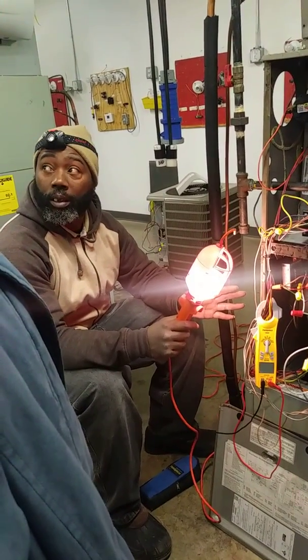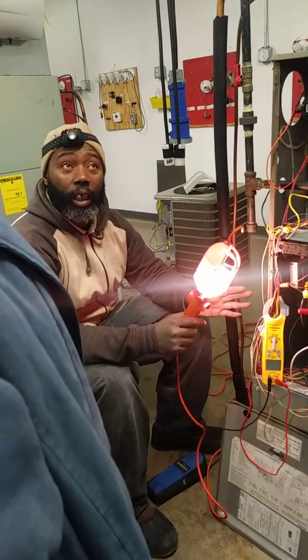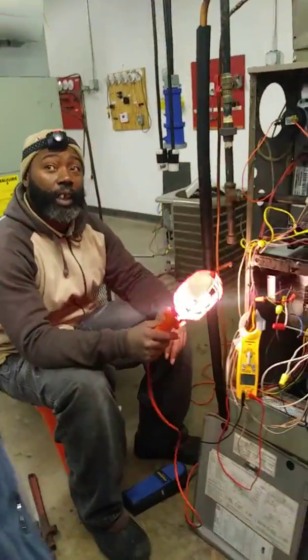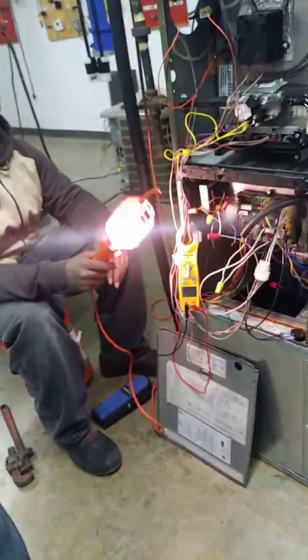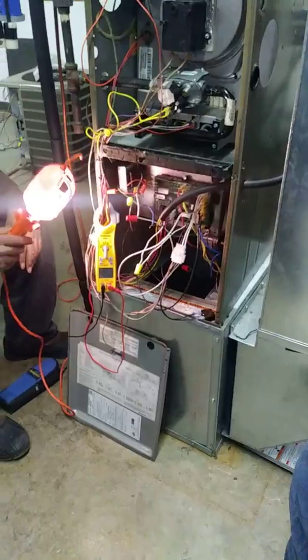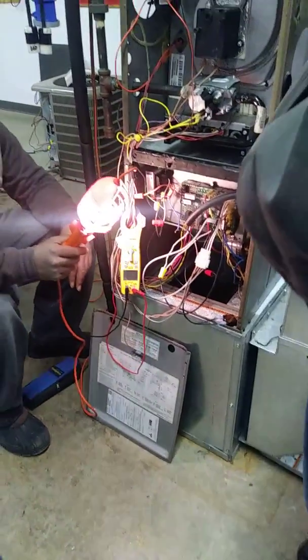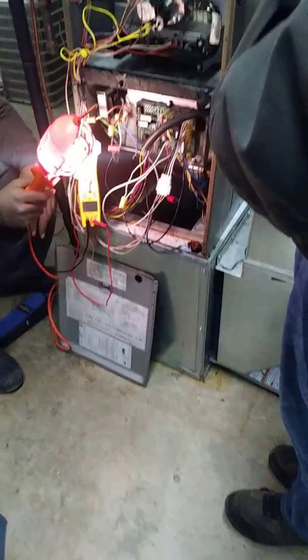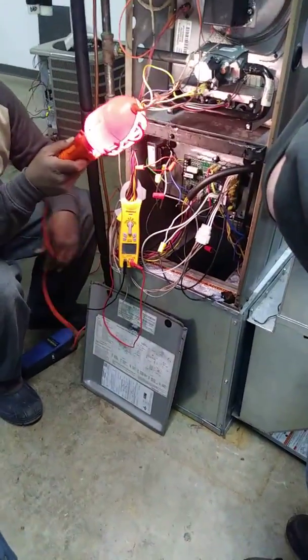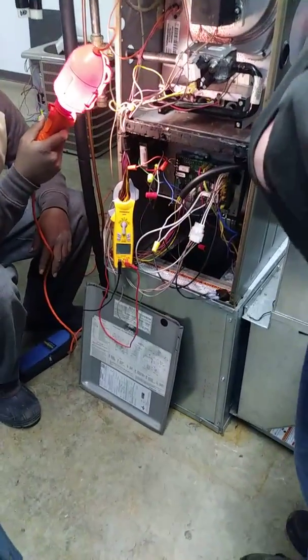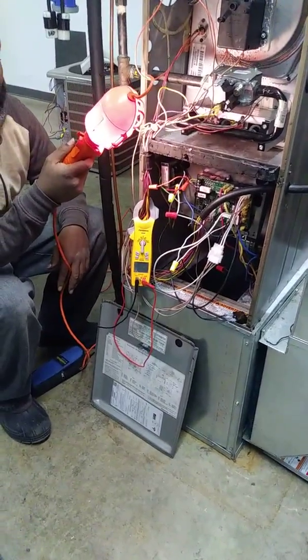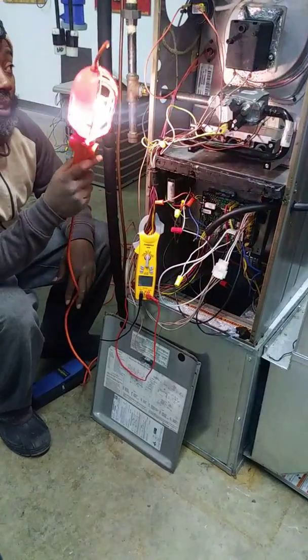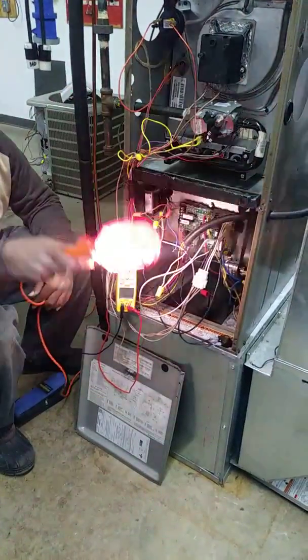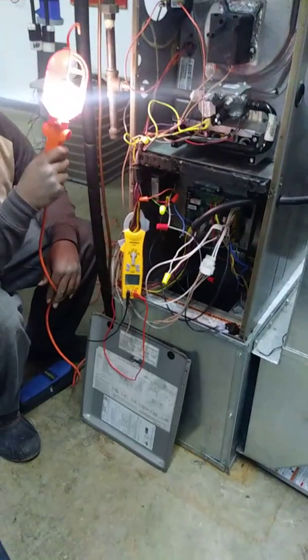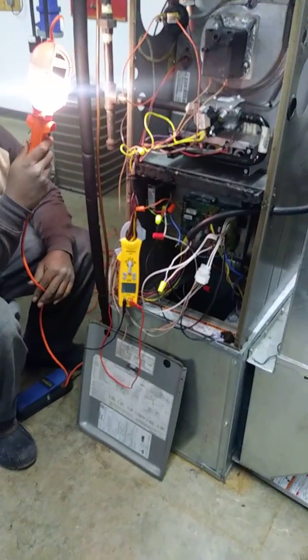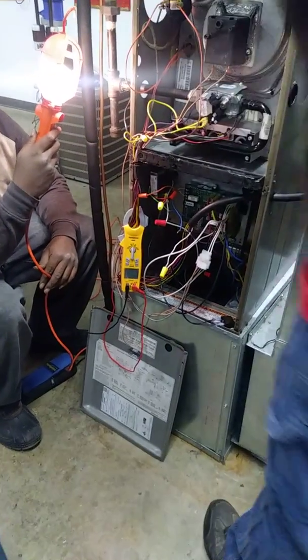Is the blower kicking on? Is it even coming on? After you try so many times, then the blower kicks on. It will kick on. Most of the time it will. But if it's going for 5 to 10 minutes, or even a couple of minutes, it could be a dirty filter, or it could be a clogged A coil.